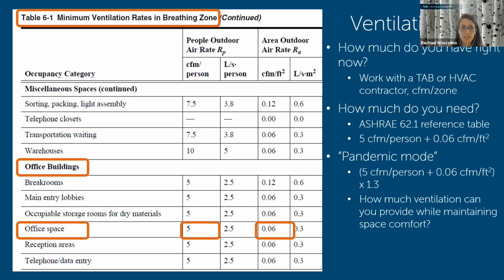And some buildings, depending on how sophisticated their control system is, are saying, let's just bring in as much ventilation as we possibly can, as long as the other indoor air quality parameters are not thrown out the window. So how much ventilation can you provide while still maintaining a space set point that feels really comfortable to the occupants? Because if we just bring in a ton of ventilation air, you're not going to have any accumulation of aerosols, but you're going to drive that temperature down, you're going to drive the RH down, and that's going to impact other transmission risks. So it really is a balancing act.